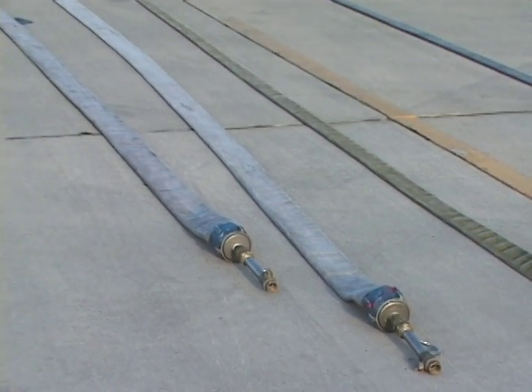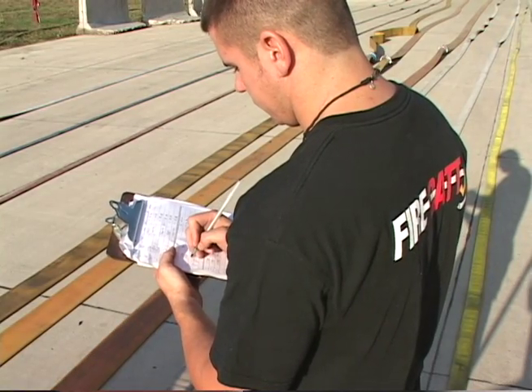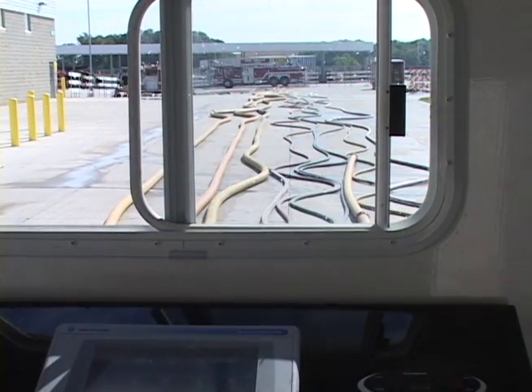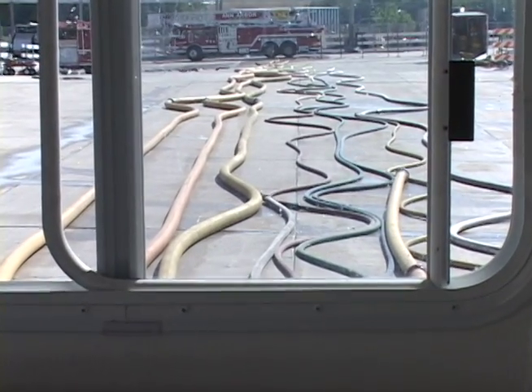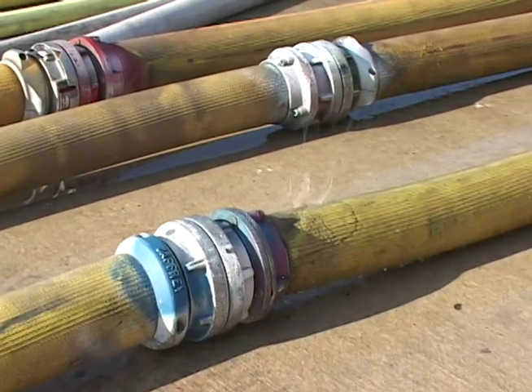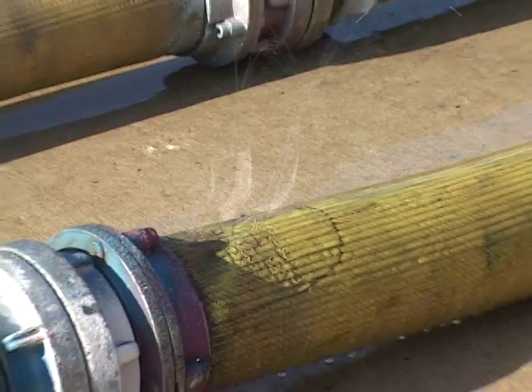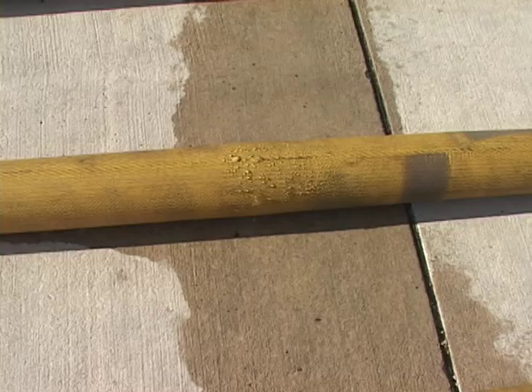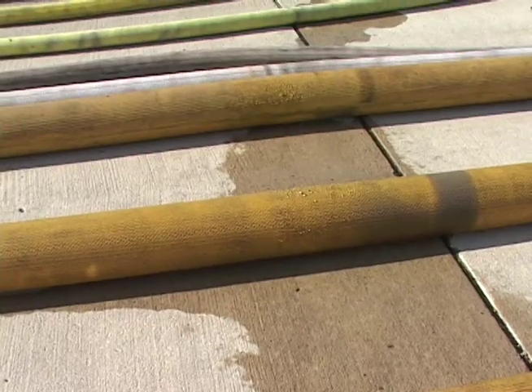Then I push a button and it begins to pressurize the system. The system pressurizes up to the lowest pressure manifold requirement, shuts that valve, goes to the next pressure, shuts that valve, and it goes all the way up to the highest pressure. Once it reaches that set point, it shuts the whole system down and we wait for three minutes. At the end of three minutes, we reboost the hose according to NFPA and bring it back to the set pressure point, then wait another three minutes.